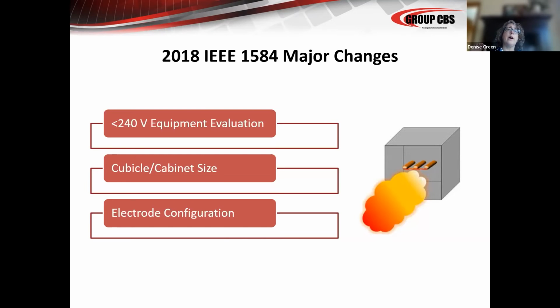In 2018 IEEE came forward with a lot of changes in the calculations for incident energy and arc flash distances. The previous revisions to the formula had happened in 2002. So over 16 years, they looked at the coefficients that they were using for cubicle size and decided that they were still seeing arc flash incidents, maybe unexpected arc flash incidents. So they set out to determine formulas that would take into account the cabinet size and the electrode configuration, and they also found that they needed to add a consideration for equipment 240 volts and below.